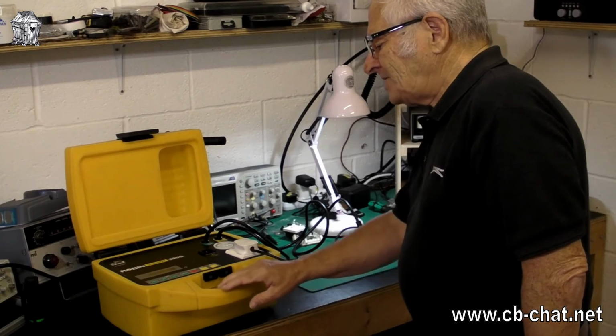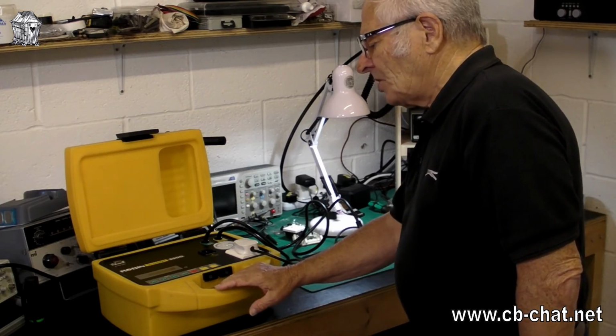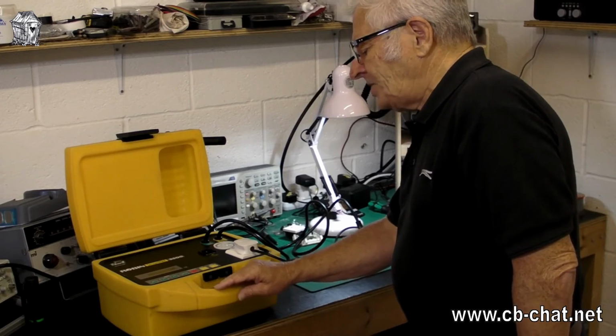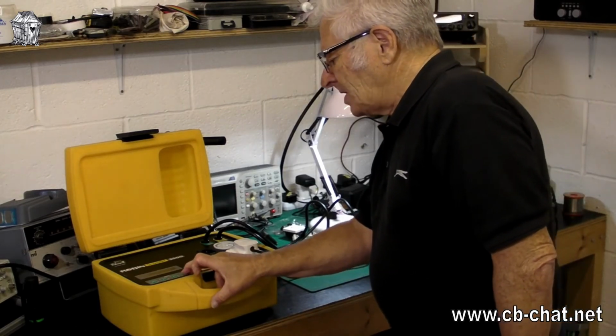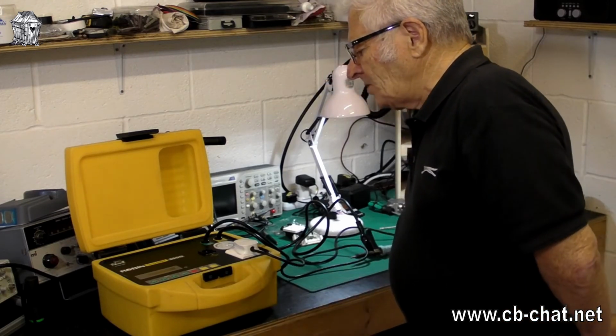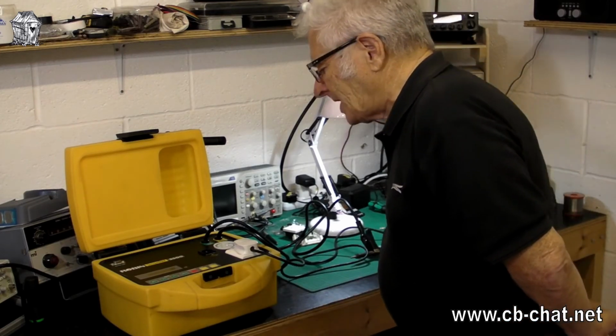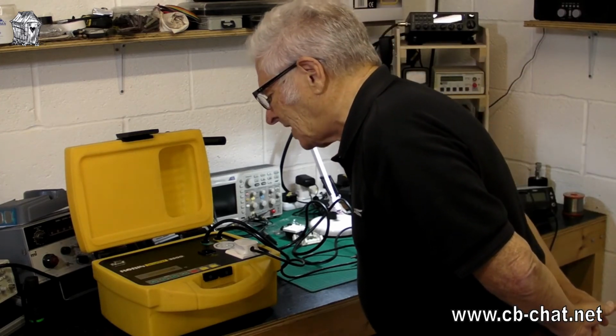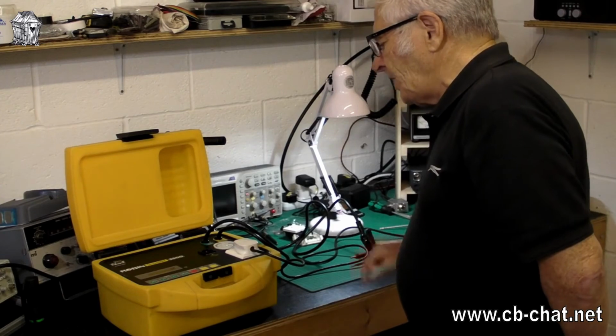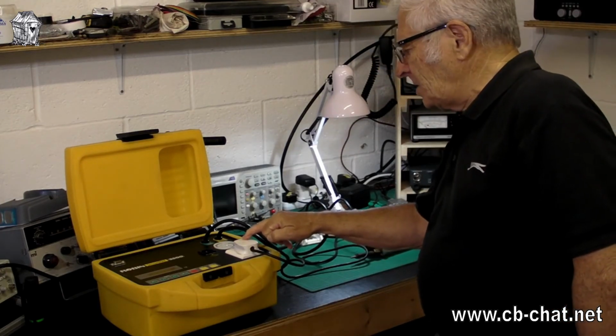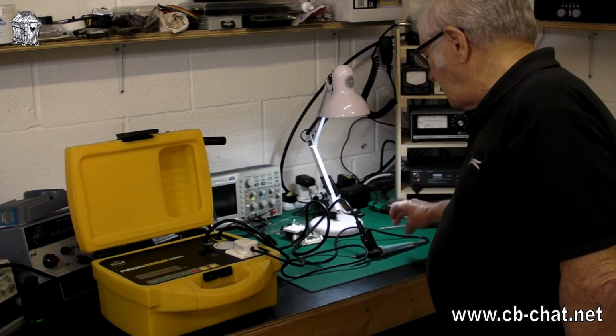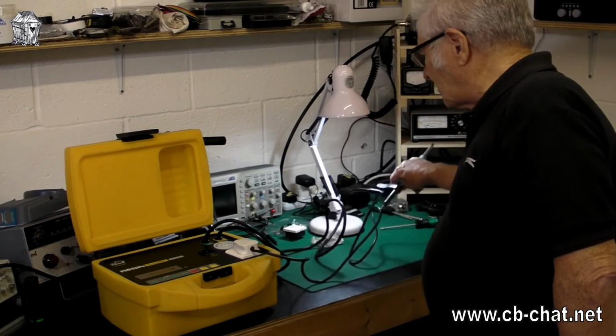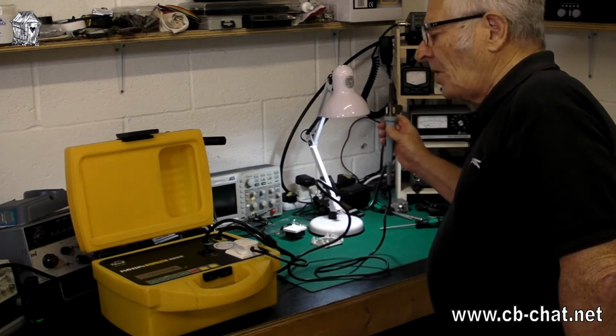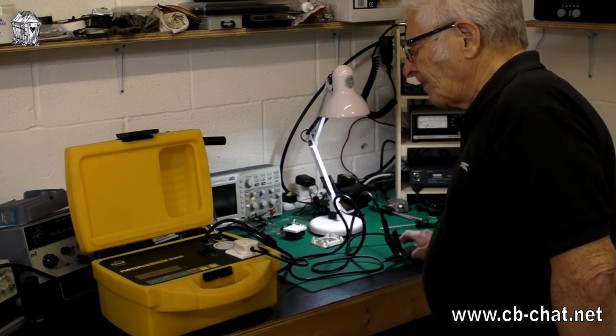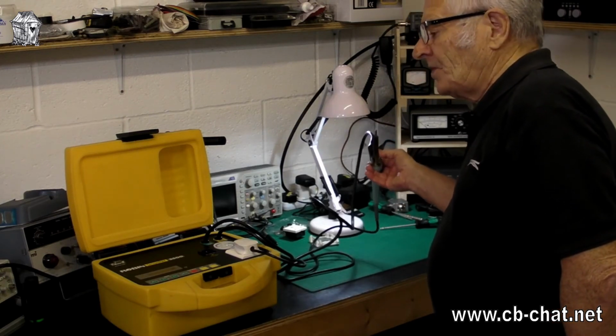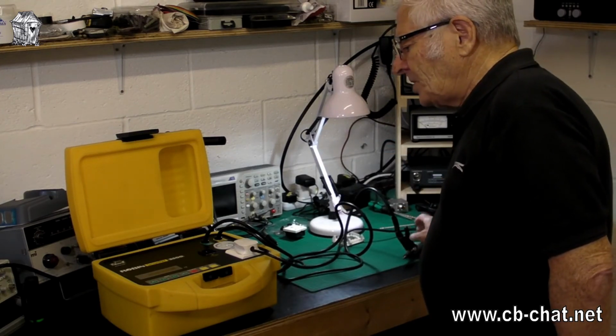And then the next test we're supposed to do is the earth bond. And again, the value of fuse comes into this to a certain extent. If it's IT equipment, delicate equipment, we can do that, and it only puts 100 milliamps down the device, down the earth wires, and it's checking to see what the resistance is, and it's saying it's 0.12 of an ohm. So from the earth pin of the 13 amp socket here, right down to the device, then back from the metal of the device, through that crocodile clip, and back to the tester, it says it's 0.12 of an ohm, and that is a pass. It's got to be less than 0.25 of an ohm.